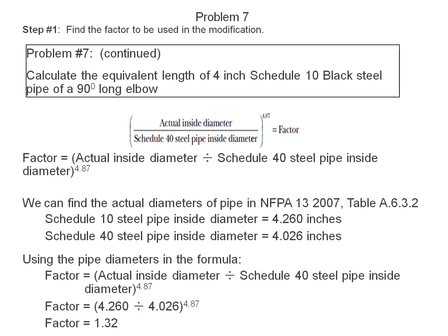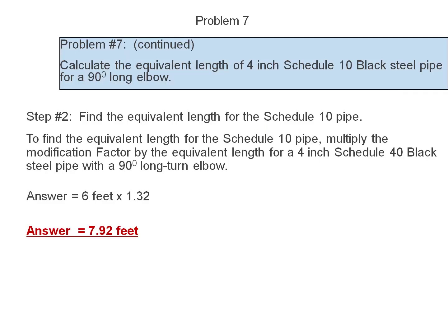The solution to problem number 7 can be found by using Table A.6.3.2. Schedule 10 steel pipe inside diameter is equal to 4.260 inches. Schedule 40 steel pipe inside diameter is equal to 4.026 inches. Using the pipe diameters in the formula to find the factor, it's equal to actual inside diameter divided by Schedule 40 steel pipe inside diameter to the 4.87 power. We divide 4.260 by 4.026 to the 4.87 power and our factor is 1.32.